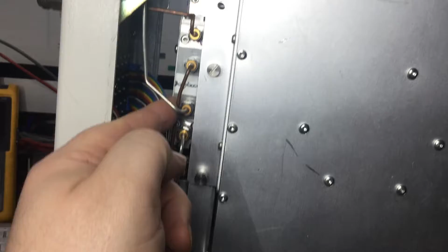So we've got again another module there bolted to this chassis, and that was quite an extensive RF module. It's got its own supply there with that connection. This ribbon cable here is the DC power supply connection, and then we've got RF going in there, and not sure if there's something going off at the top. Couldn't see, don't think so. So I wonder if that's where the reference power is produced, perhaps, because if I reach round the top, there's no coaxial cable connecting to the top of that module. So I think that's where the reference power is produced to self-calibrate. So that's where the calibration standard is, basically.